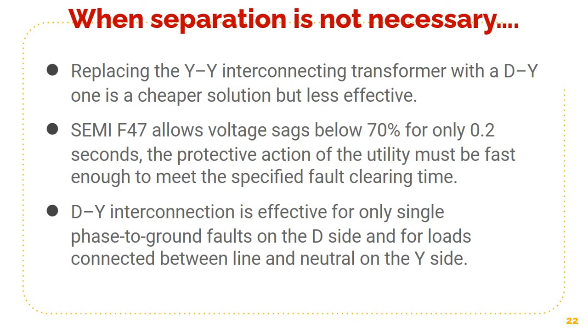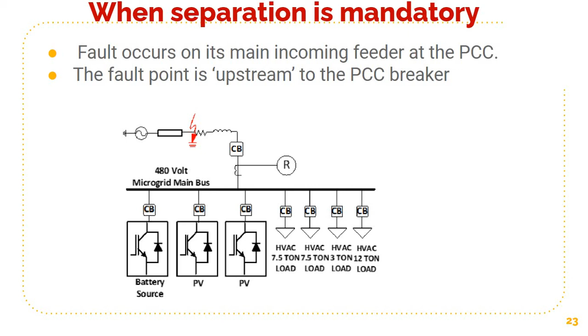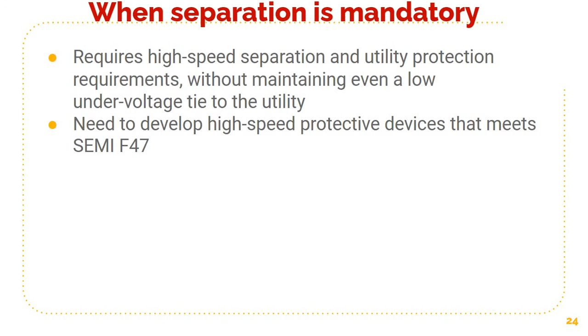Now sometimes the separation is mandatory. For example, if the fault occurs on the main incoming feeder at the PCC, that is at this particular point, so the fault point is upstream to the PCC breaker. In such a case, the separation is mandatory. The microgrid should be immediately separated from the utility grid. So we need high speed separation and utility protection requirements without maintaining even a low under voltage tie to the utility. So there is a need to develop high speed protective devices that meet SEMI F47.